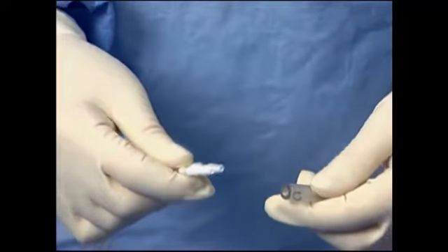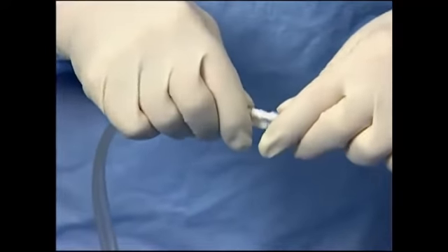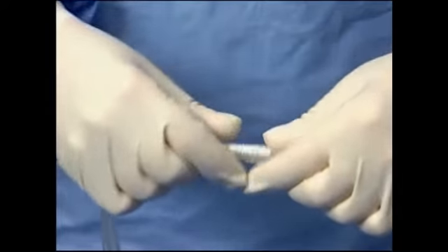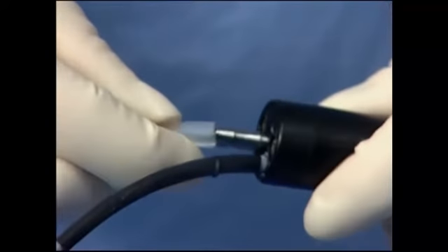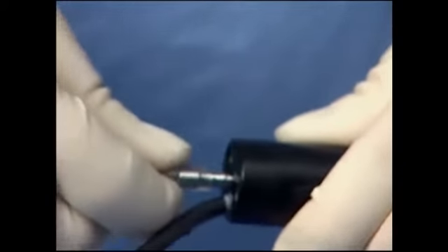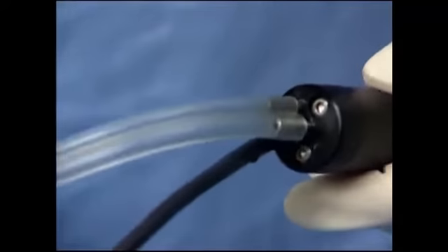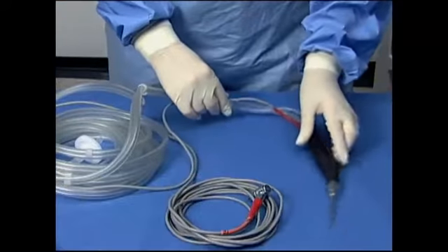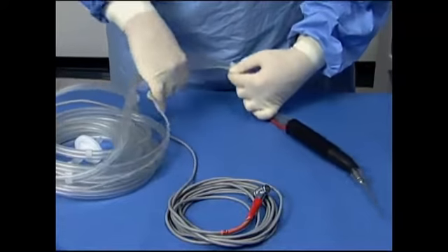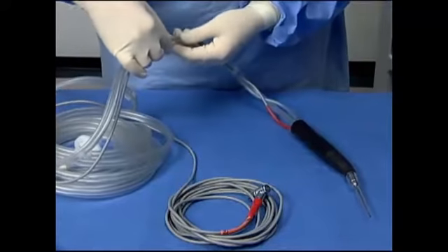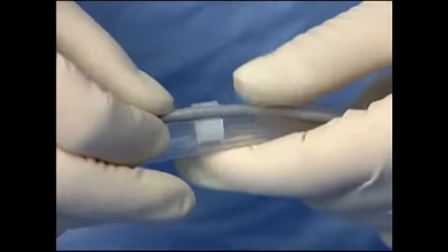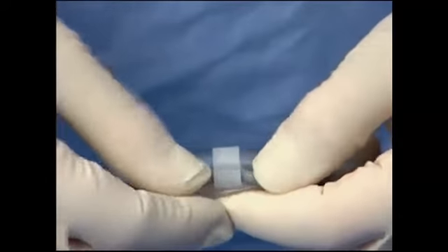Attach the white connectors on the mini tubing kit to the open end of the tubing kit. Connect the other end of the mini tubing set to the irrigation and aspiration ports on the back of the microsurgical handpiece. Using the sterile white hose clips on the tubing set, attach the handpiece cable to the tubing set. Tubing clips are spaced at convenient intervals and can be adjusted as desired.